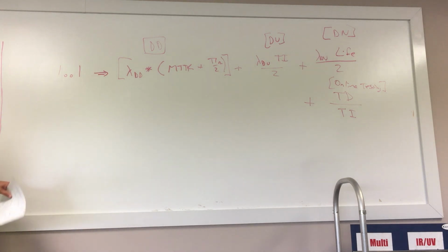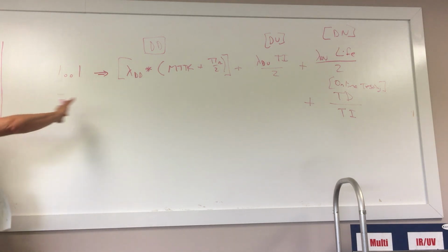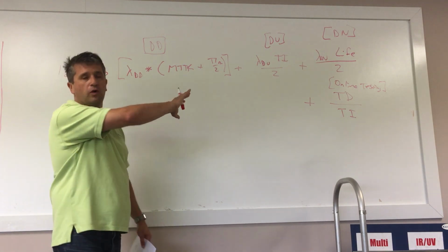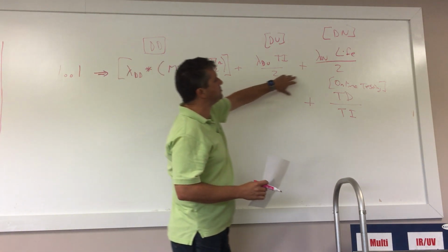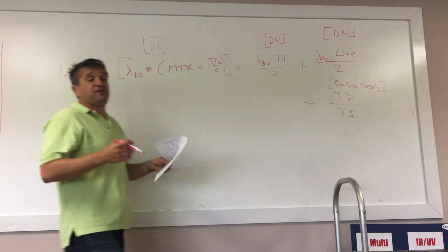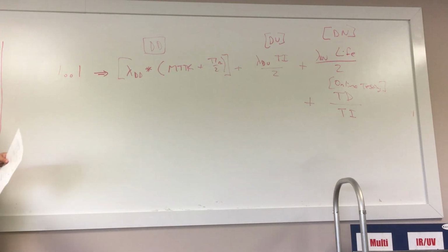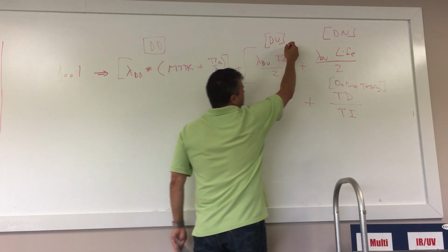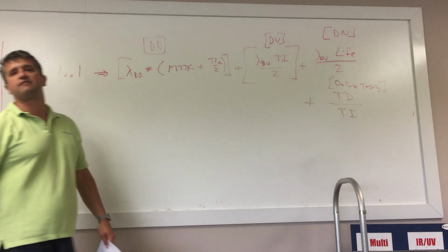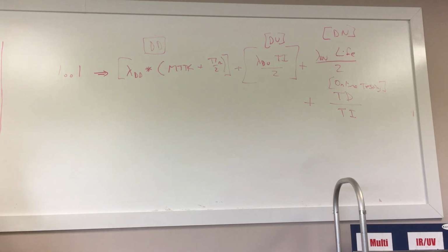So when we're calculating the overall PFD of a 1-out-of-1 or a simplex system, we need to evaluate all of these terms. But if you look at, for instance, the early version of ISA 84's technical report on how to perform PFD calculations, it only contains this one term and none of the others. So why is that?